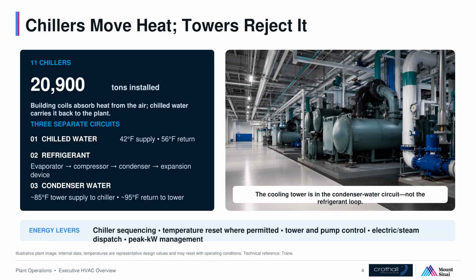A chiller does not make cold. It moves heat. Building coils absorb heat from the air, and chilled water carries that heat back to the plant, typically around 42 degrees Fahrenheit leaving the plant and 56 degrees returning, although operating targets can reset. Inside the chiller, a separate refrigerant circuit runs from evaporator to compressor, condenser, and expansion device. Then a third circuit, condenser water, carries the rejected heat outdoors. Water may arrive from the cooling tower near 85 degrees and return to the tower near 95. The tower belongs to the condenser water circuit, not the refrigerant loop.